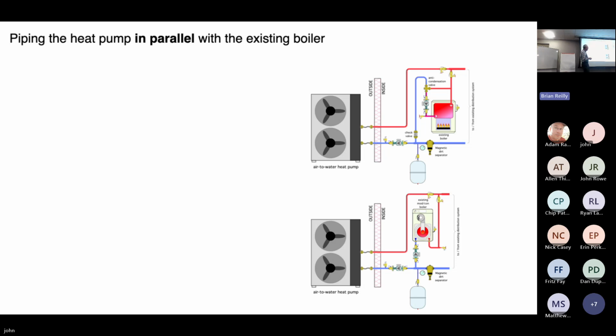So what's necessary, you don't have to throw the boiler away, but you do want to install what's called an anti-condensation mixing valve. And it's a very simple device. It's a thermostatic valve. And what it will do is measure the temperature of the water coming back from the distribution system. If this is below about 130 degrees, it's actually going to block that water off, and this pump is going to be on. The water's going to do this as the boiler warms up.